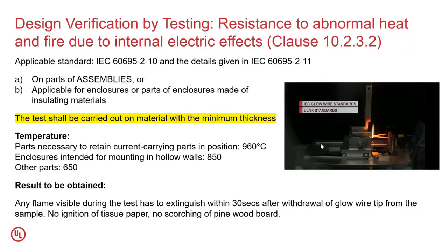The acceptable limit is that any visible flame has to extinguish within 30 seconds after withdrawal of the glow wire tip from the sample. There should be no ignition of tissue paper and no scorching of pine wood, as per the procedure of the standard. But basically, this refers to the glow wire test.